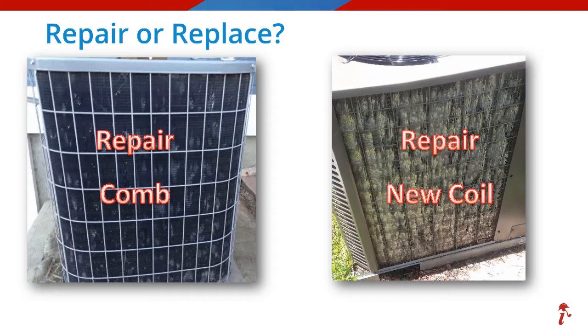Replacing coils is an often overlooked repair action, but very often the right one and is an industry accepted repair — done probably every day somewhere during hail season. It would be very hard to make claim decisions on these types of claims using just photographs. An on-site inspection would be preferable, as you or a technician could make the determination if what you are looking at is repairable or indeed a replacement is warranted.